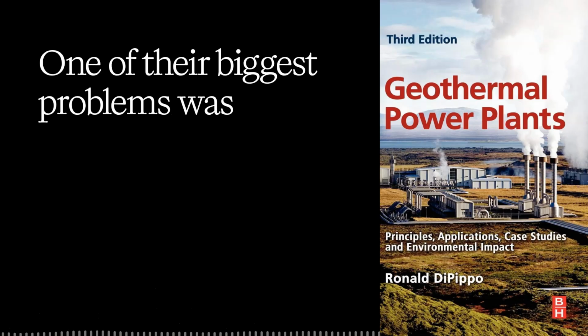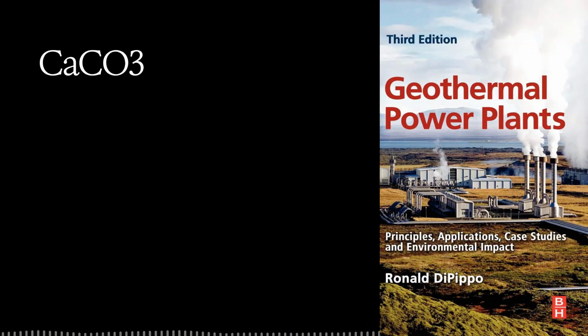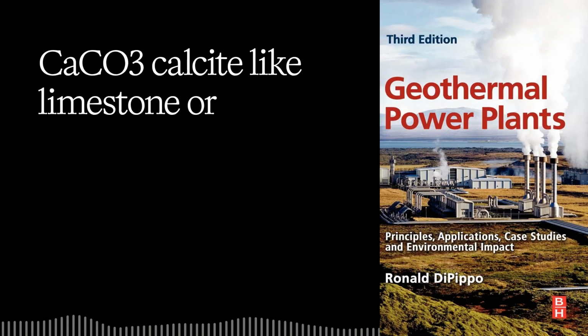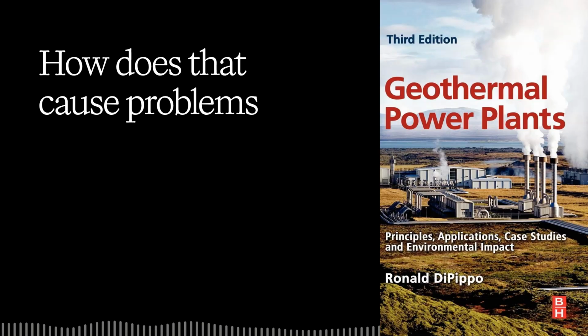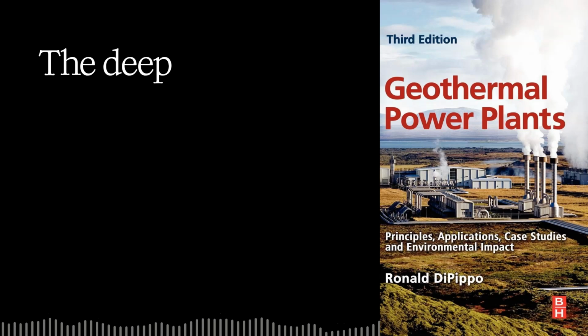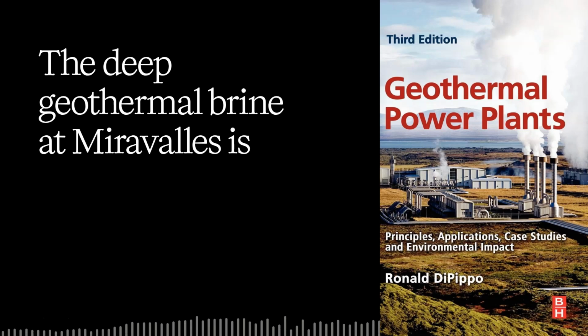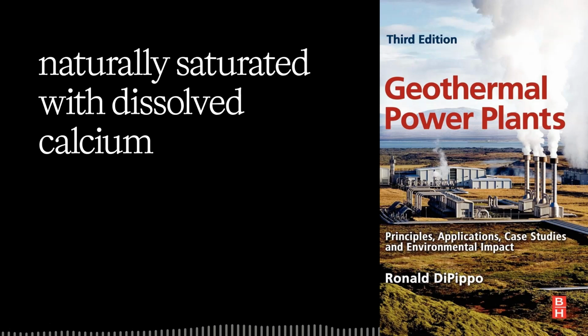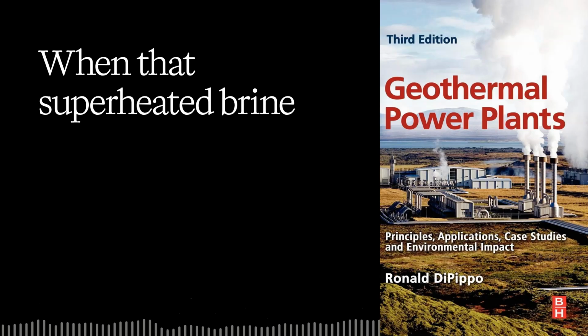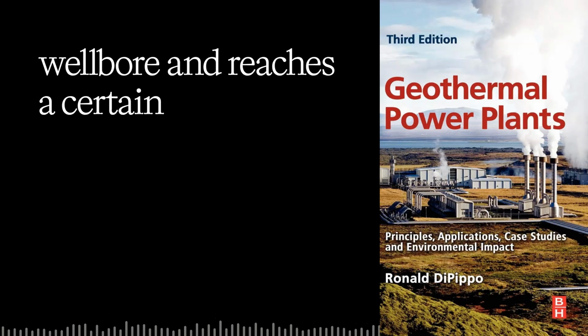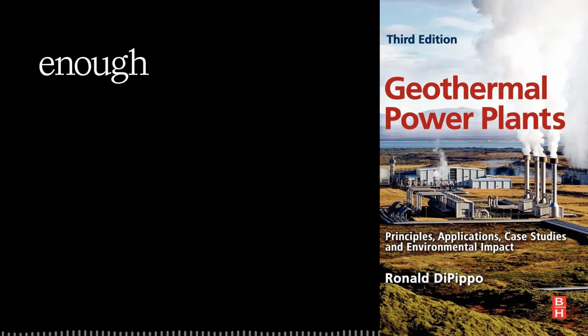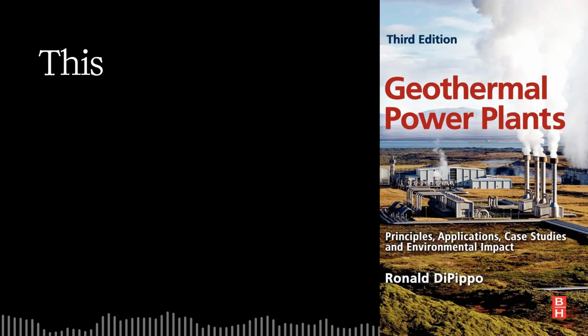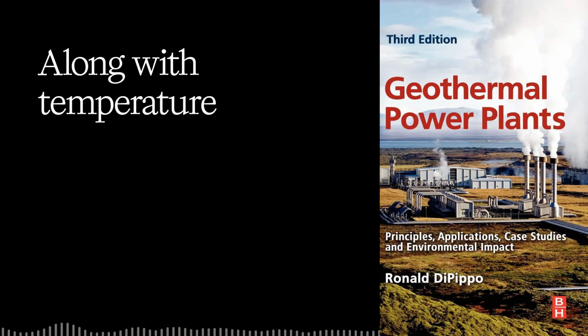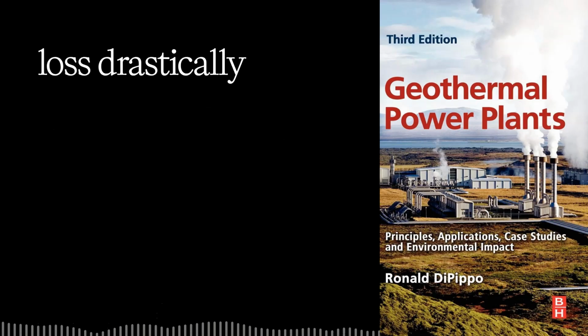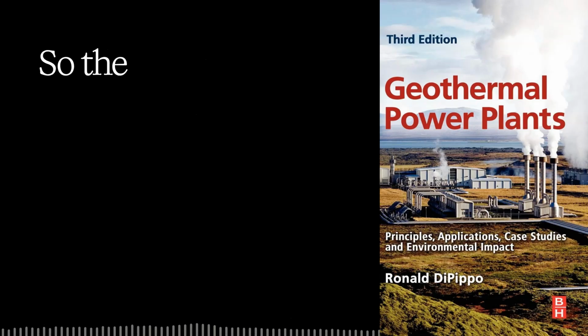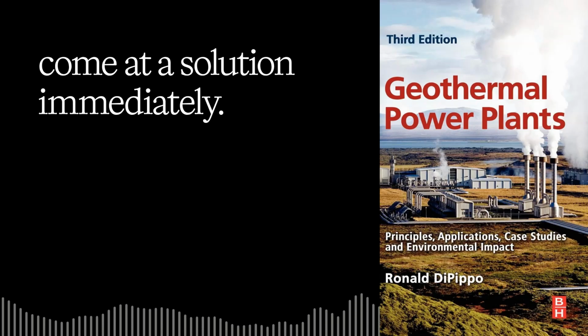One of their biggest problems was calcite scaling, calcium carbonate, CaCO3, like limestone or chalk. How does that cause problems in a geothermal well? Well, the deep geothermal brine at Miravalles is naturally saturated with dissolved calcium carbonate. When that superheated brine flows up the wellbore and reaches a certain depth, the pressure drops enough for it to start flashing into steam. This rapid pressure drop, along with temperature changes and CO2 loss, drastically reduces the solubility of CaCO3, so the calcite suddenly wants to come out of solution. Immediately, yes.